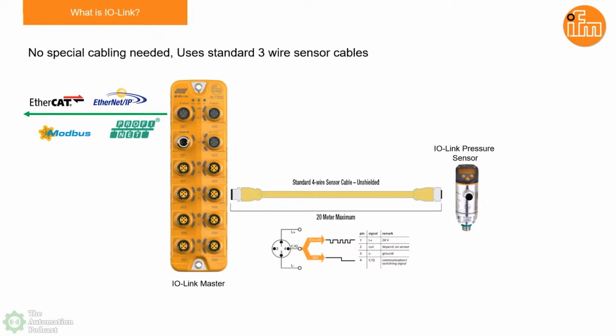What's also unique with IOLink technology is that you don't need any specialized cabling. As you can see here, your connection from the IOLink sensor to the IOLink master just uses a standard 3-wire sensor cable, the typical cable you're using in any of your installations today. That doesn't change. So the nice thing about this technology is that your current wiring and hardware, for the most part, will stay the same.